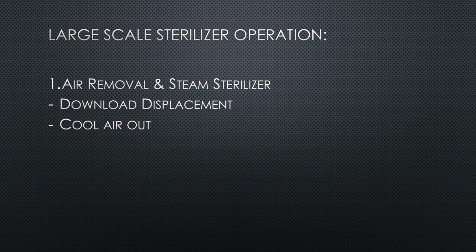This has the benefit that whatever load is there gets warmed, which aids the heating up process. Its application is in the sterilization of bottled fluids, where bottle breakage may occur under the combined stress of evacuation and high temperature.